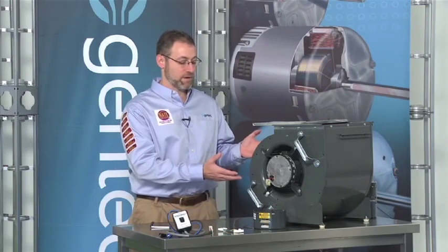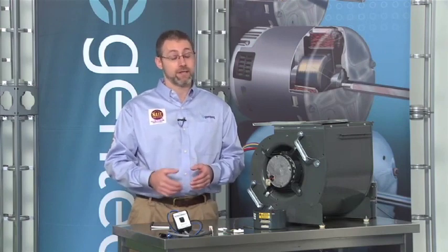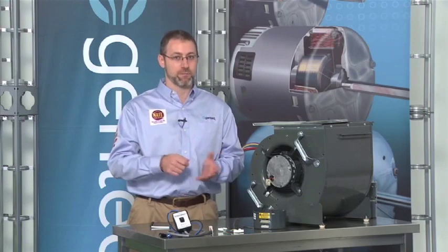When you're finished with any service call, especially one where a part had to be replaced, it's a good idea to check all of the wiring connections in the system. In the case of our motor, often the blower section will have to be pulled out, which means wires had to be disconnected and reconnected on the main circuit board. Good idea to check them and make sure they're all back in the same place. This will also get checked if you run the system in both heat and cooling to make sure that everything works properly. I always like to check all the safeties in any system, make sure they're working the pressure switches, the limit switches, that kind of thing. And all of the drain hoses from the air conditioning system, from any 90% furnaces, even from humidifiers. Just make sure all the drains and all the traps are free and running clear.